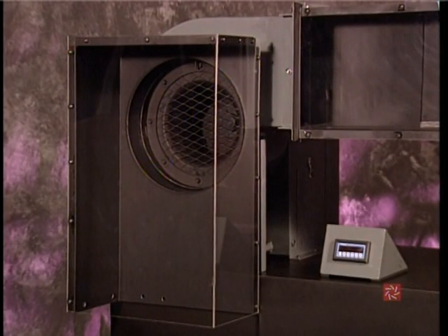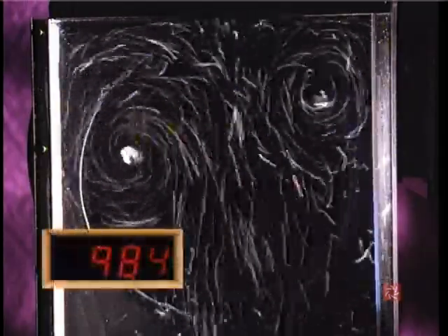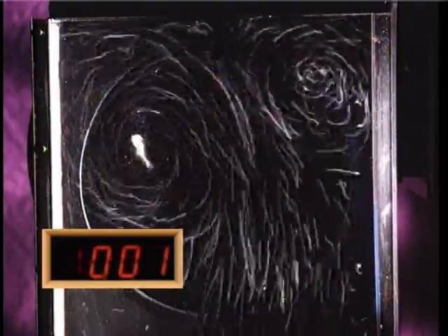Occasionally, space limitations do not allow the designer to provide a straight inlet to the fan. Many times, this type of fitting is attached to the fan inlet. With this type of duct connection, a counter-rotating vortex appears. In this case, airflow has been reduced approximately 45%.